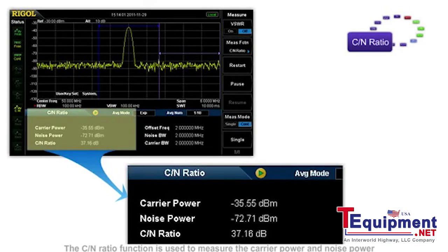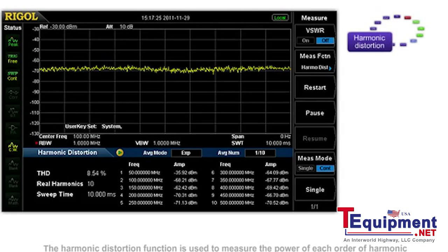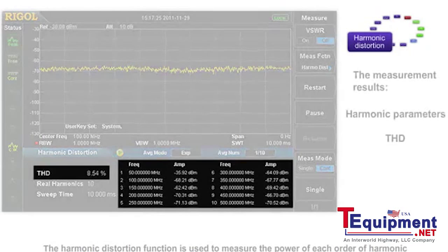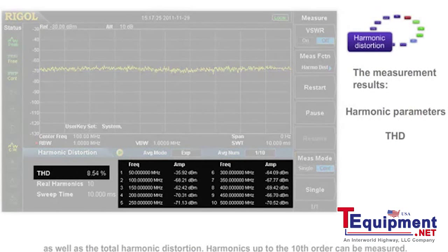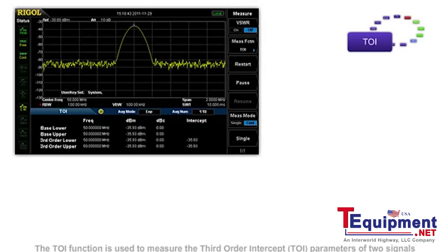The C to N ratio function is used to measure the carrier power and noise power within the specified bandwidth, as well as the ratio. The harmonic distortion function is used to measure the power of each order of harmonic as well as the total harmonic distortion. Harmonics up to the tenth order can be measured.